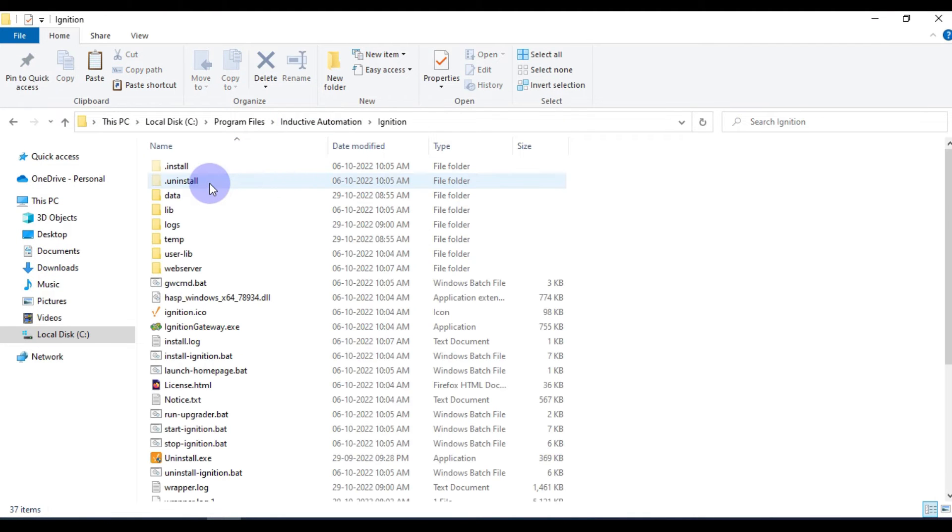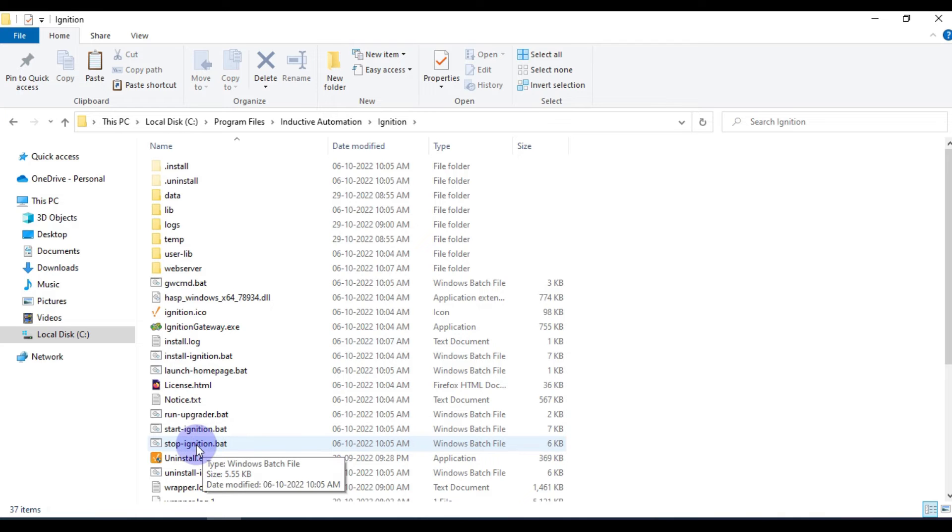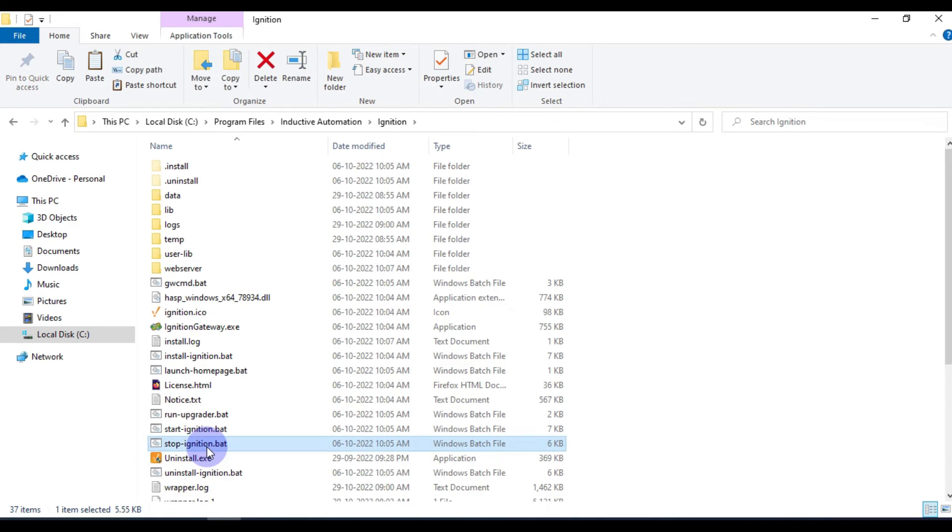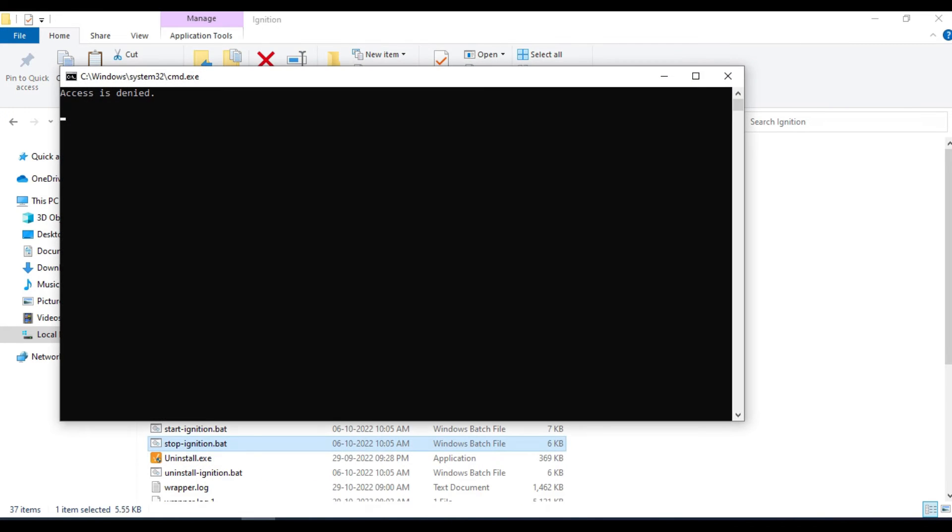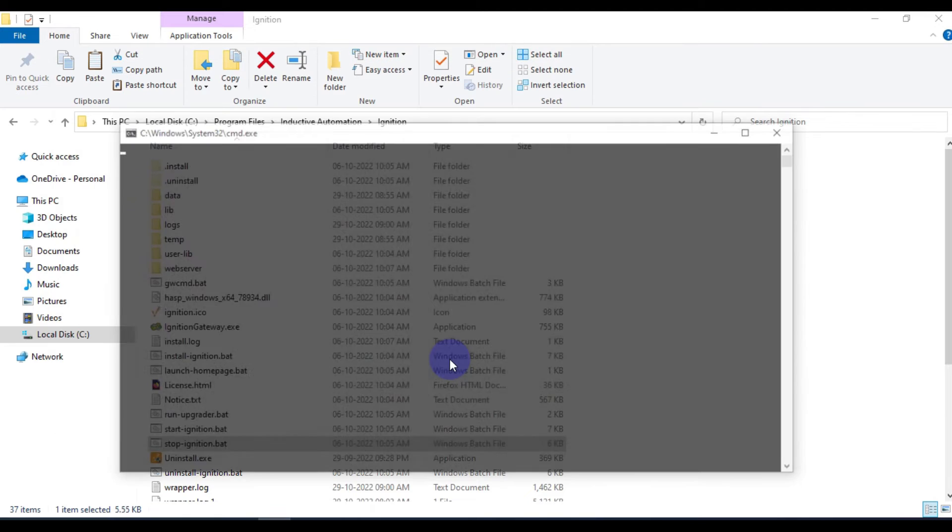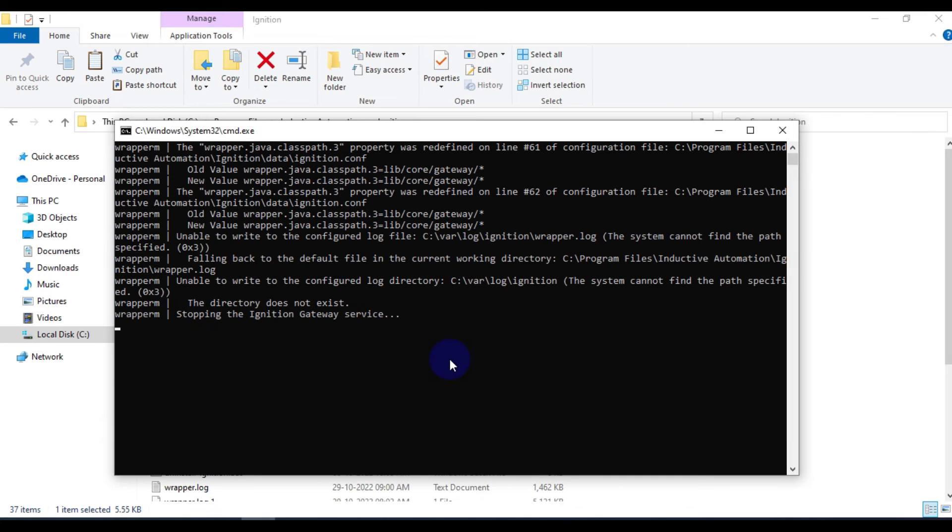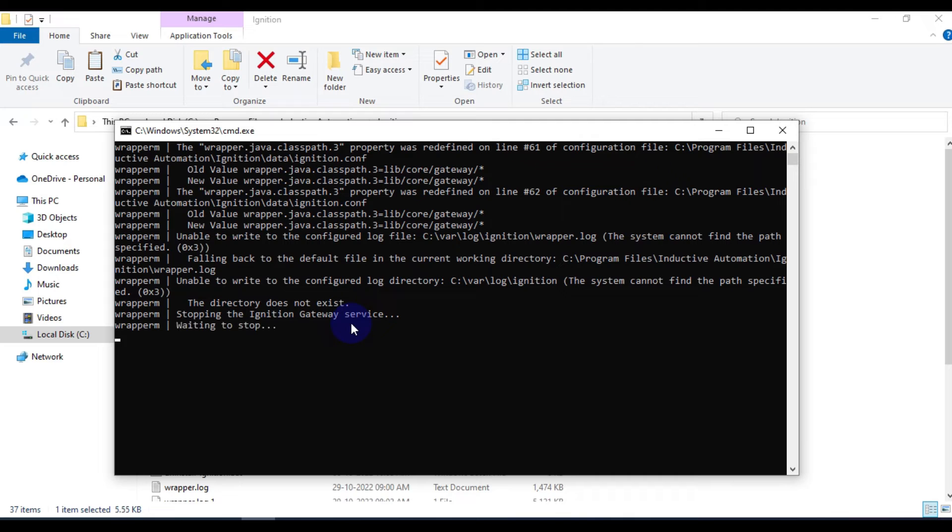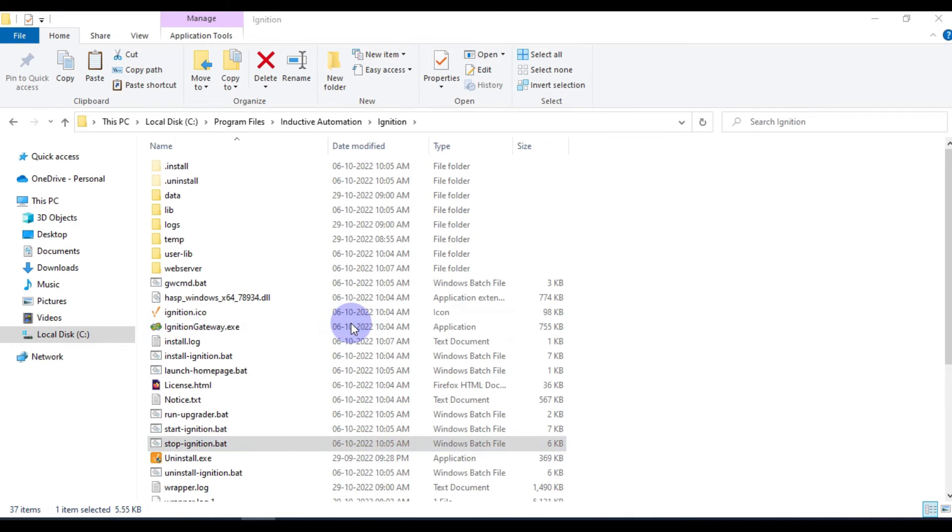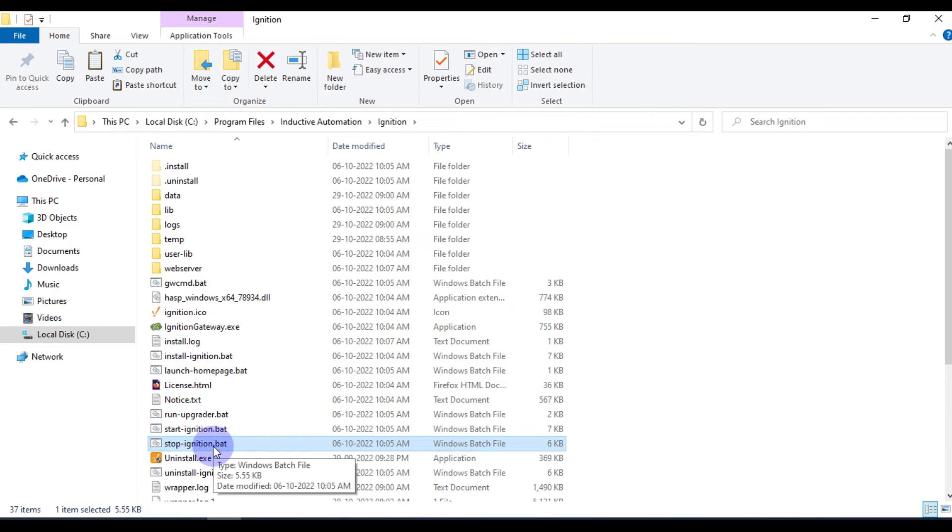You have to stop the Ignition using this batch script. So stop ignition.bat, we have to run the script. Stopping the Ignition Gateway services. Once the gateway service is stopped, you have to restart again to apply the effect of your time zone. Our Ignition Gateway services are stopped.